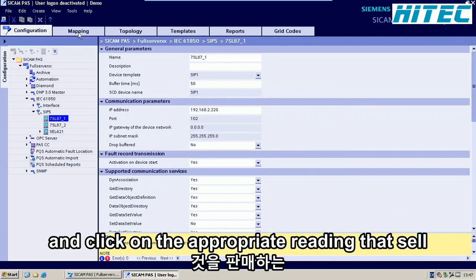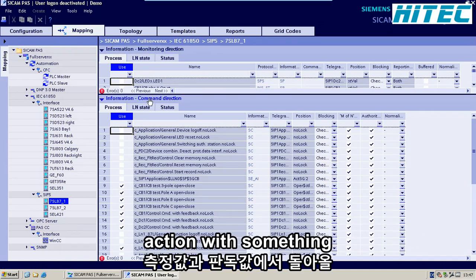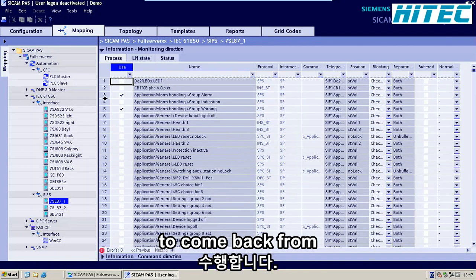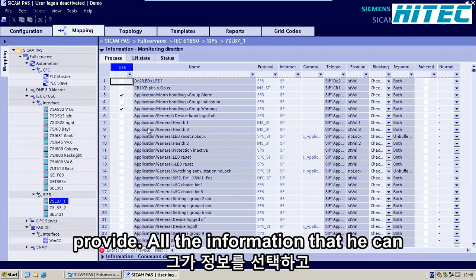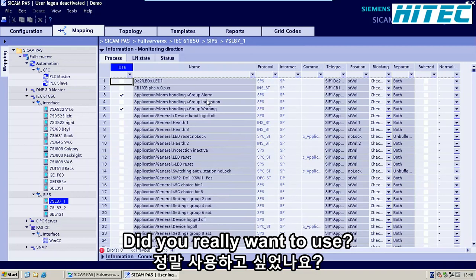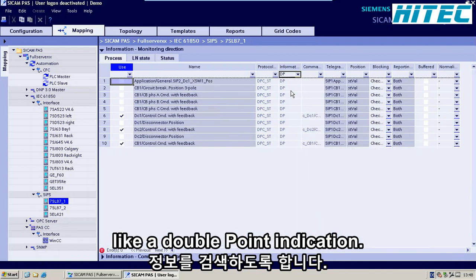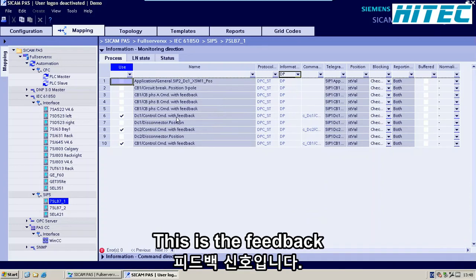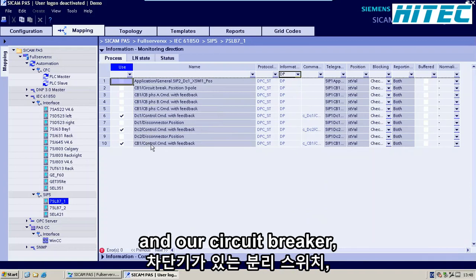To see the mapped data, go to Mapping and click on the appropriate relay — let's say the first one. There you have a monitoring direction and a command direction. The monitoring direction covers measurements and indications that come back from the relay. Here you can pick and choose the information you want to use in SICAM. The IEC 61850 server provides all information and you can filter as needed. You can see single point information, and use filters to search for double point indications. Here you see Disconnect 1 — the feedback signal — Disconnect 2, the line disconnect switch with its feedback signal, and the circuit breaker feedback signal.